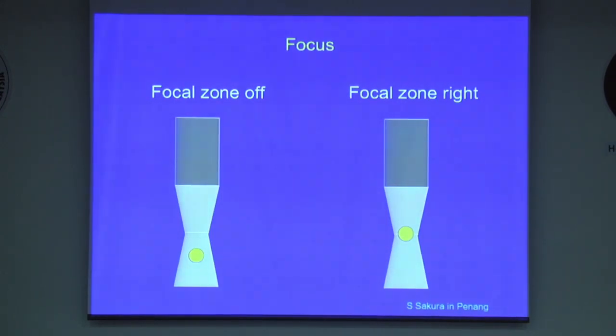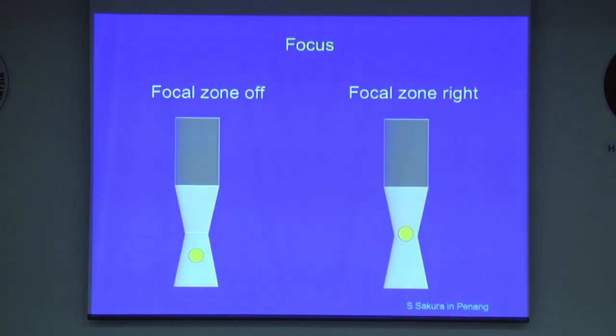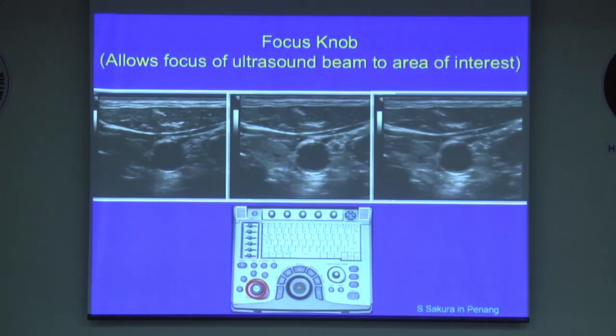Ultrasound beams can be focused, like light focused through a lens on a camera. The focal zone is where the greatest beam strength and intensity occurs and the image resolution is the greatest. So it is very important to adjust the focus at the level of the target, because that is where the needle tip is approaching.